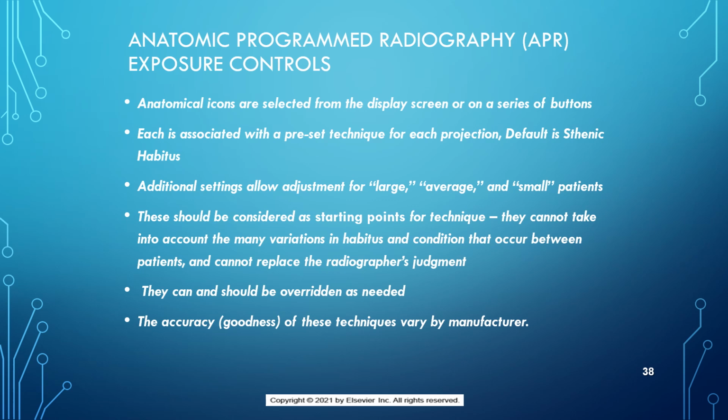Okay, the accuracy of the techniques varies by manufacturer. Like the Canon system, that's spot on. The GE, I've worked with the GE Digital, the default GE techniques. Those are rock solid. 95% of the time, those are working.